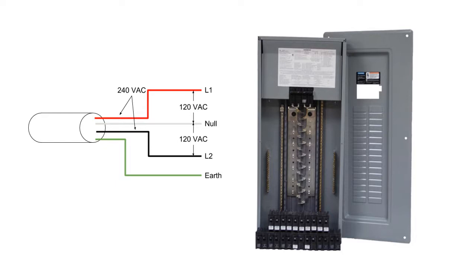An electrician connects L1, L2, null, and earth wires provided by the utility company according to code. If you want to know more about how to make proper connections, there are plenty of videos on this topic on the internet. Often you will hear that we have a 110 volt supply in North America. That's at the outlets and takes into consideration potential losses in voltage from the panel through the wires to the outlets. Some household appliances such as stoves and dryers require 240 volts AC to operate. The 240 volts is from the unsplit L1 and L2.